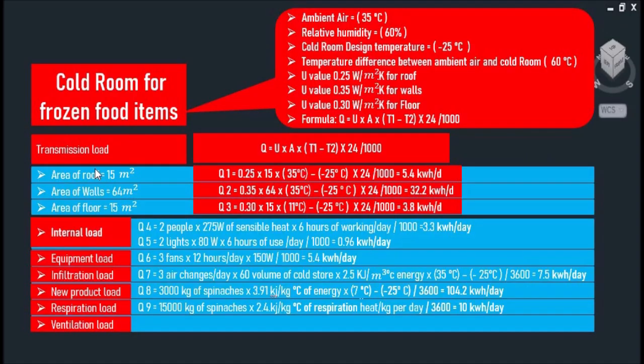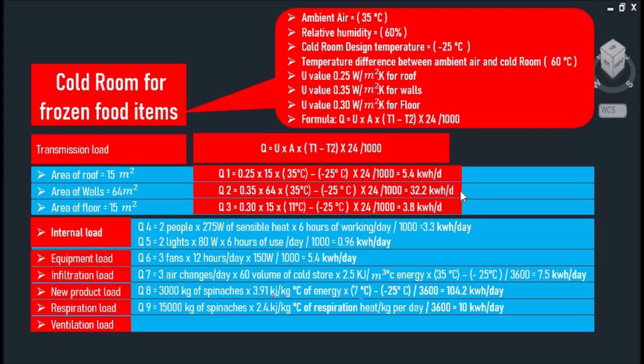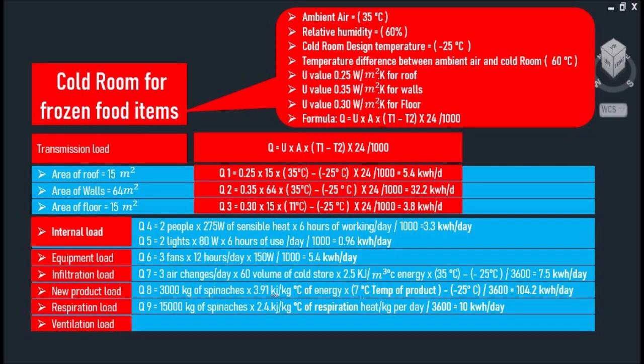As you can see, I have already calculated the transmission load through our roof, walls, and floor: 5.4 kWh per day for our roof, 32.2 kWh per day for our walls, and 3.8 kWh per day for our floor.